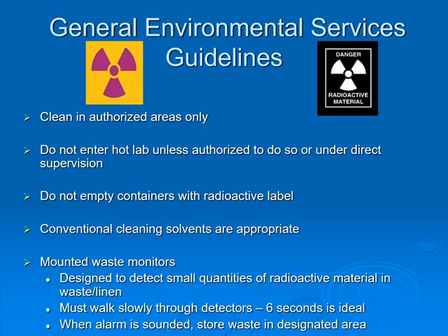Some facilities have mounted waste monitors. These monitors are designed to detect small quantities of radioactive material in the waste and linen. It is important to walk slowly through these detectors. At least 6 seconds is ideal. When the alarm is sounded, store the waste in the designated area.